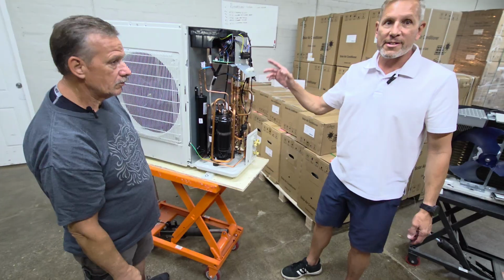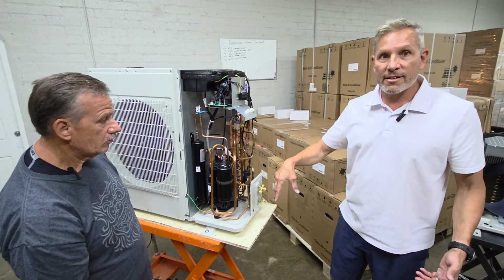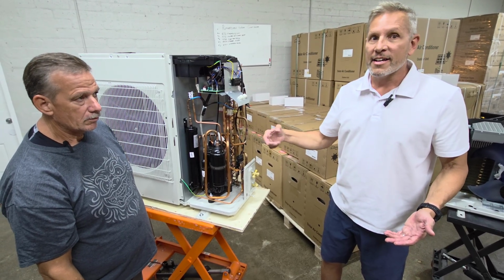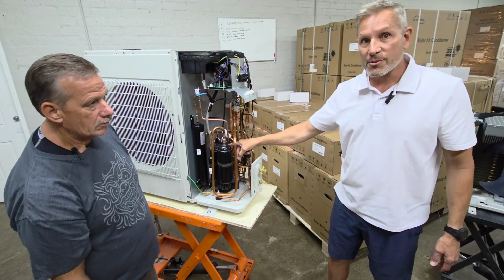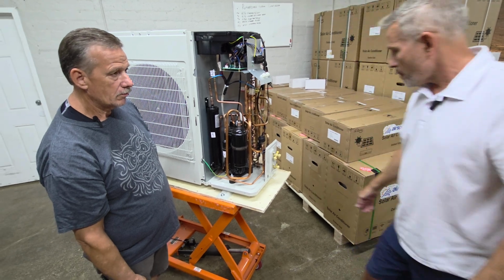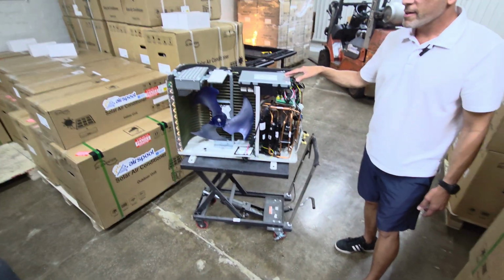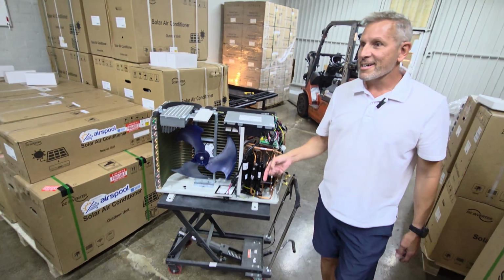So hopefully that makes sense. So you have this refrigerant. You're taking some of it to make the liquid refrigerant colder, and you're taking, I don't know what percentage, but a small percentage to make the liquid refrigerant that came in, changing state of that and making that into a gas and warming up that gas. So you have a little bit of gas coming in through the compressor that is warmer than it would be if it just came from this outdoor unit here. And so this is the same thing, only different. This is a 12,000 BTU unit, and this is a 24,000 BTU unit. So, yeah, what else do we need to talk about here, Todd?